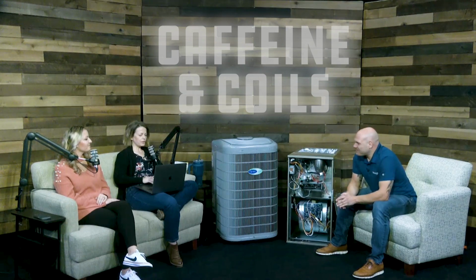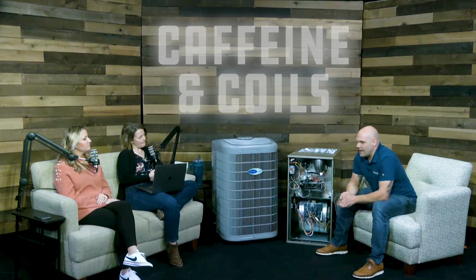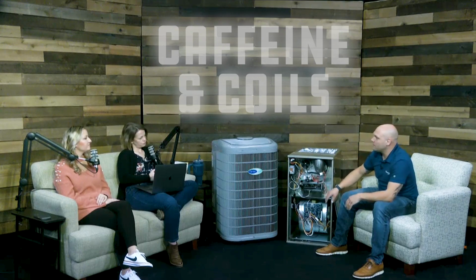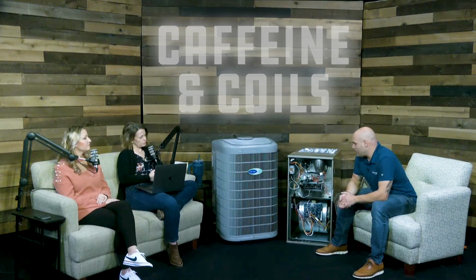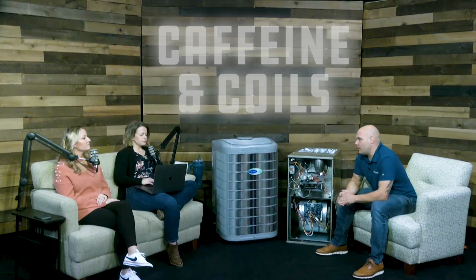All right, so you told me a little bit before about the 7 steps that are involved in the furnace process. Do you want to tell us about that for technicians that might need to know about troubleshooting? Sure. This is kind of standard for gas furnace troubleshooting. I call it the heating sequence, and there's 7 steps. If you are troubleshooting, the first thing you want to do is really start over. So turn the furnace off, cycle the power to it, and then when you turn it back on, the first thing you want to look for is the actual call from the thermostat.